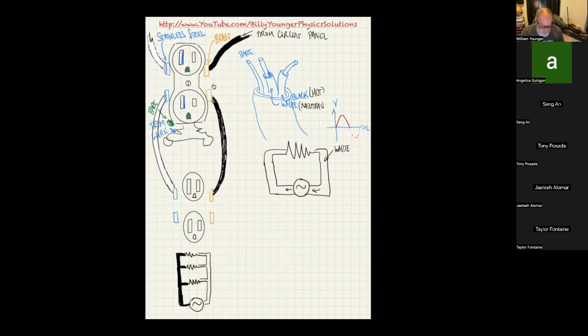Now, this receptacle has all sorts of cool features. Not only does it have a spot where you can trim the wire, but on the back there's a little divot showing how long you're supposed to trim the bare wire. In other words, you cut the housing off the black and white wires, and the bare wire sticking out should match exactly the length shown on the back of the receptacle.